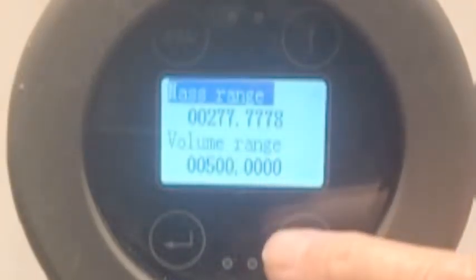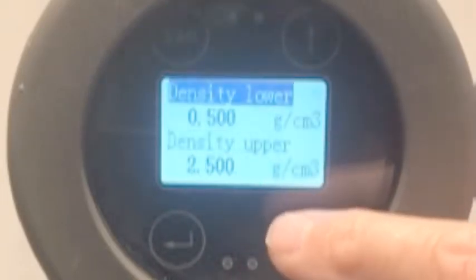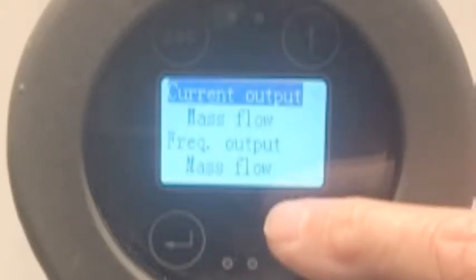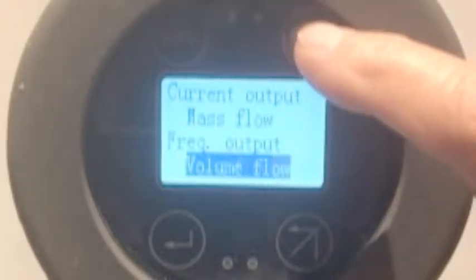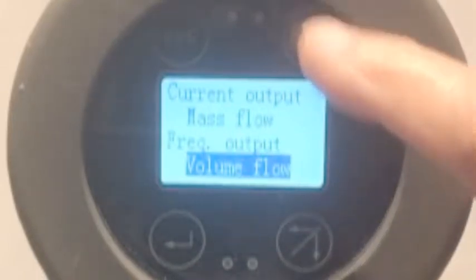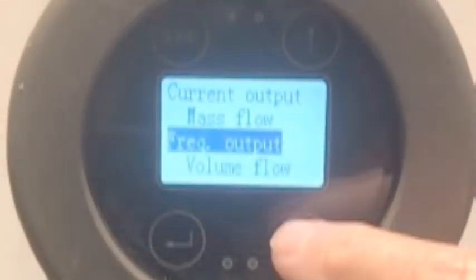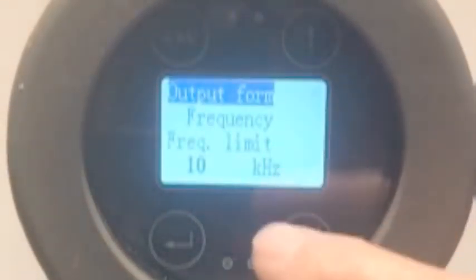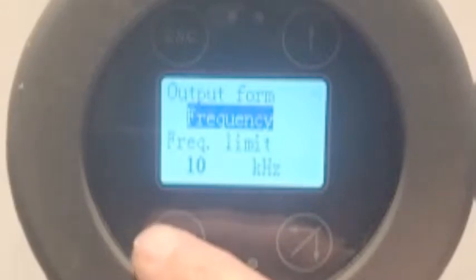I can look at all these other settings: the range, the volume range — this is when the 4-20mA works — and if you have the 4-20 and the frequency output. Lower density, upper density. Current output, frequency output. Enter. We can change that to whatever we want: volume or mass. The same thing is true for the current output, with current output being mass flow. The output from frequency — enter — we could choose either pulse or frequency. Frequency is most common, and the frequency output on this one is 10 kilohertz.